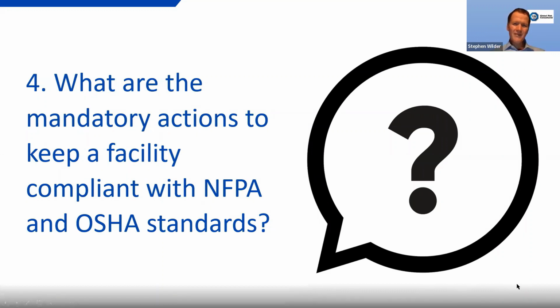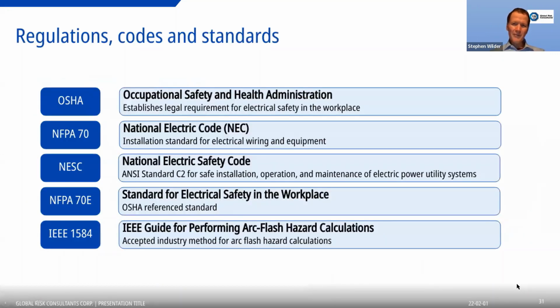Yeah, this is somewhat controversial. The National Electrical Code requires a label that warns workers that an arc flash hazard exists on the electrical equipment. It doesn't require an assessment of the risk or instruct the worker what to do about it. That's all laid out in NFPA 70E. But OSHA doesn't require a specific arc flash label compliance with 70E. OSHA requires employers to have a safe work environment.